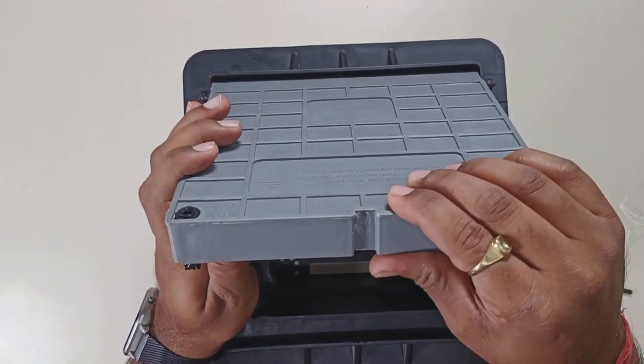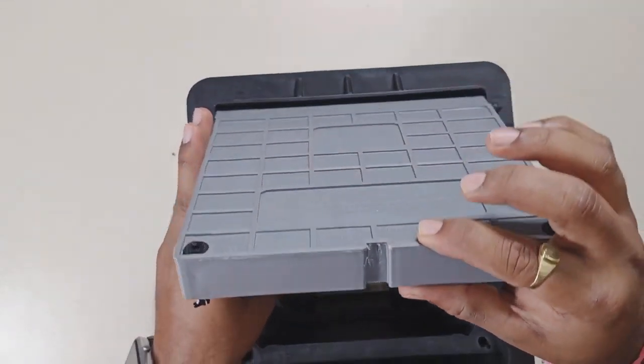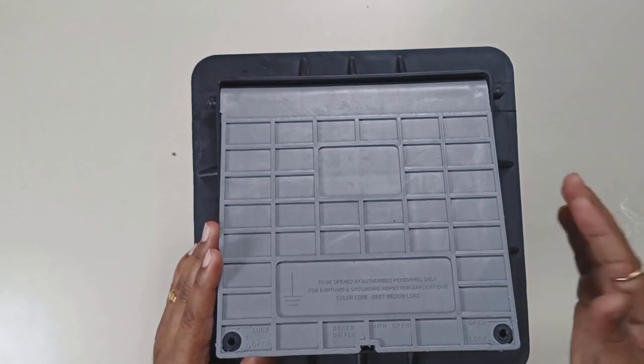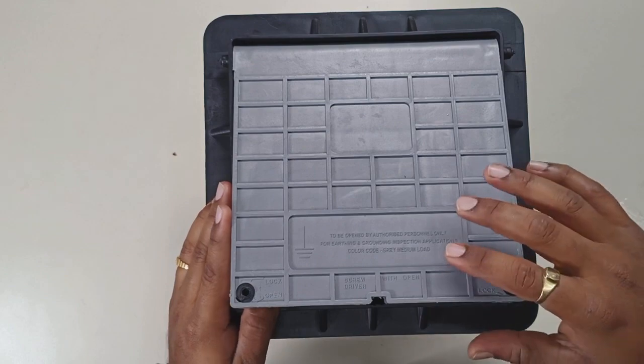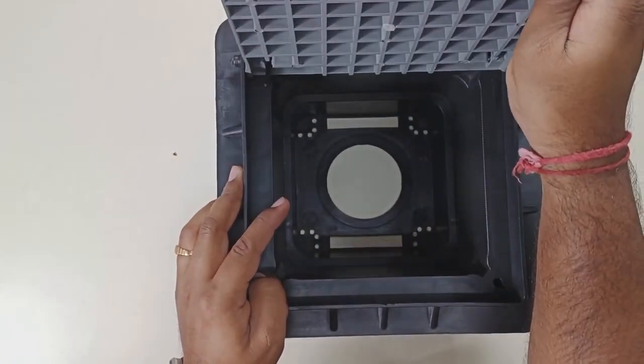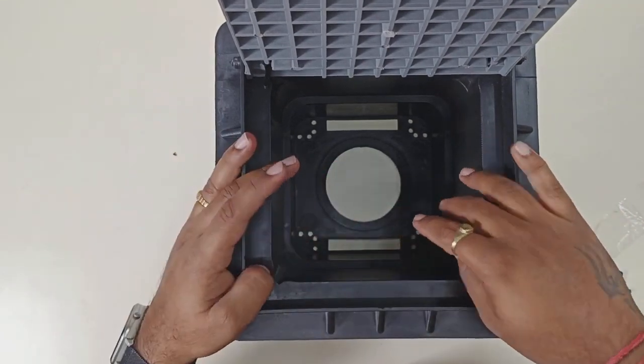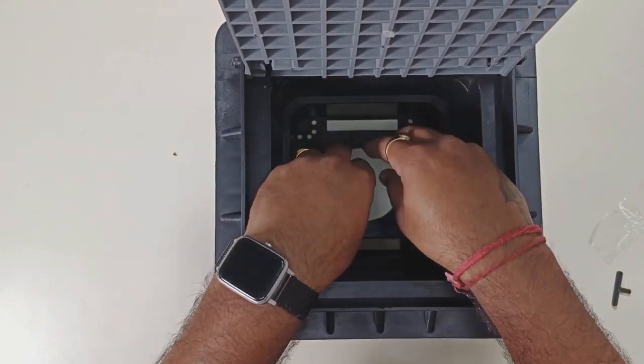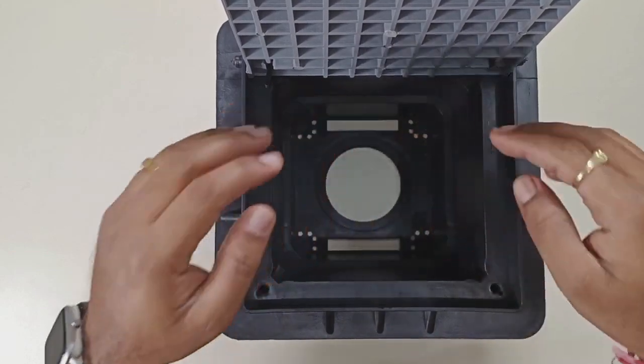The first thing I notice is that the cover itself is really solid and strong. Since this chamber goes into the ground and needs to withstand heavy vehicles, I believe that is the reason this lid is so strong and robust. I don't think vehicles should be a problem since this is heavy graded. If we are talking about the inside part of the chamber, there is sufficient space here. The earth rod goes to this circular center that you can see, and can easily be leveraged for inspection purposes.